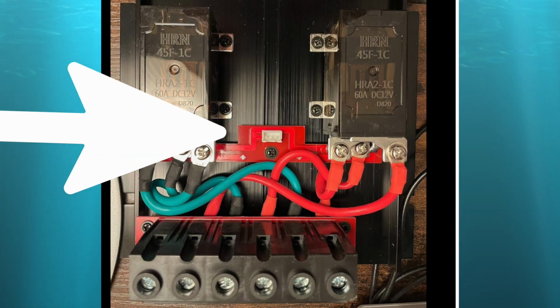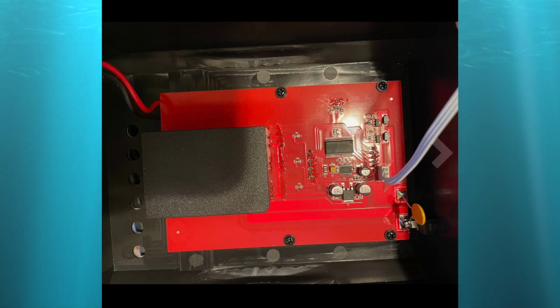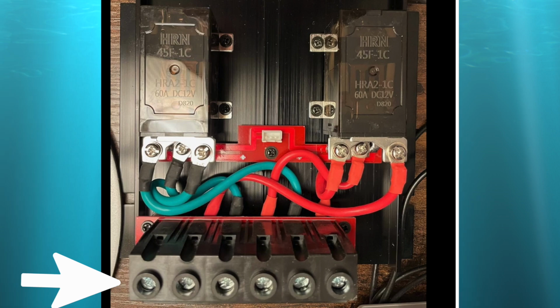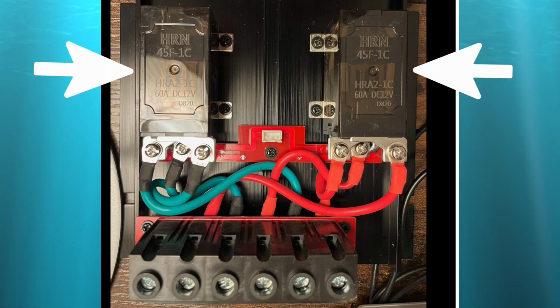So inside of this unit, this is the circuit board that runs the display and is the switching logic. This is the terminals where everything is connected, and these are just mechanical relays. The relay on the left is switching the hot circuits. The relay on the right switches the neutral circuits.